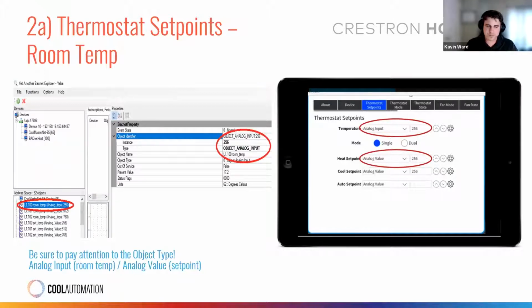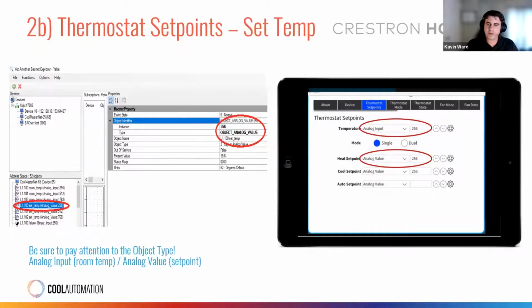This room temp is an analog input, and the set points are analog values. You can see your object list in the bottom left, the set temp, instance 256, which is an analog value. On the Crestron Home side, your room temperature is analog input 256, and your heating, cooling, and auto set points are also object instance 256, but as analog values.